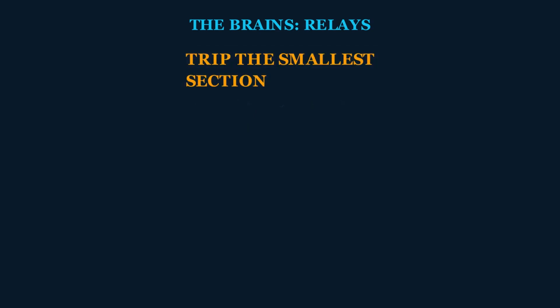This is the real intelligence of the grid, and it's why a single tree limb doesn't take out a whole city. The relays are set up to trip the smallest possible section, to open just the one breaker that isolates the fault and nothing more. Pick the tightest boundary around it, cut it out, leave everything else running. All automatically, all in the time it takes you to blink, all without a person on site.